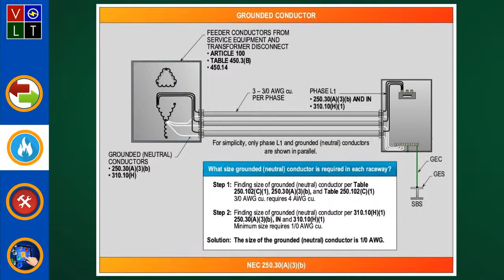Now, this is in 250.30(A)(3)(C), and this is where you deal with delta connected systems. And all it's going to tell you here is that the grounded conductor, where you have this three-phase, three-wire delta system, is that an open delta or a closed delta? Closed. Okay, and it tells you it shall have an ampacity not less than what? The ungrounded phase conductors. Yep. It's a corner grounded, right? Yeah, corner grounded. It's got to be that size where you have a delta system.